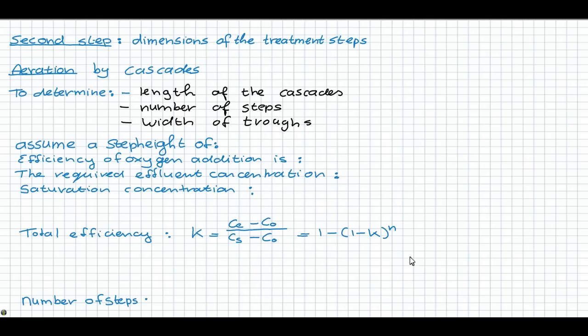The number of steps are determined by the desired total efficiency and the efficiency of an individual step. When we assume a step height of 0.4 meters, the efficiency of the oxygen addition is about 25%. You can find these values in table 3 on page 6 of the handout of aeration.